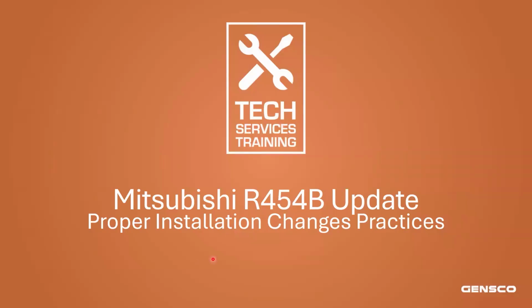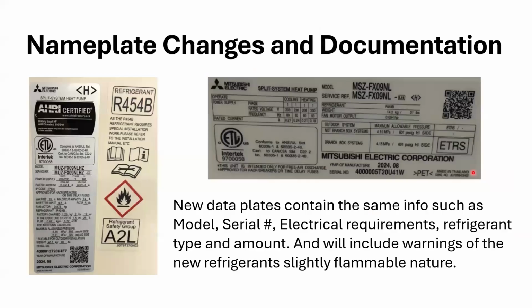Let's go with proper installation changes and practices, which is what we're going to talk about here. So, nameplate changes and documentation. This is looking at an outdoor unit, MUZFX. You're going to have your silver sticker with your nomenclature on it. It contains the same information as the model, serial, electrical requirements, refrigerant type and amount. It's going to include the warnings of the new refrigerants, their slightly flammable nature. So there's your R454B refrigerant warning, flammability, A2L, etc. That's what you're going to see now on the outdoor units.